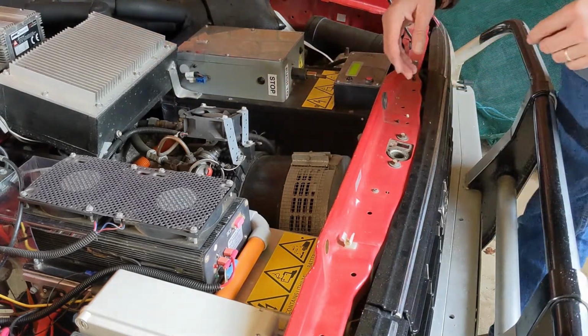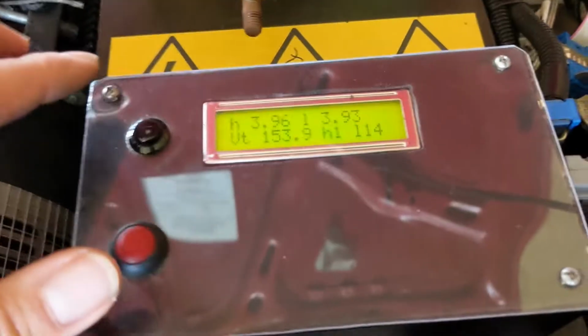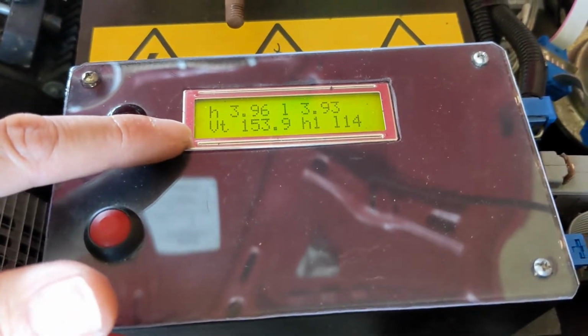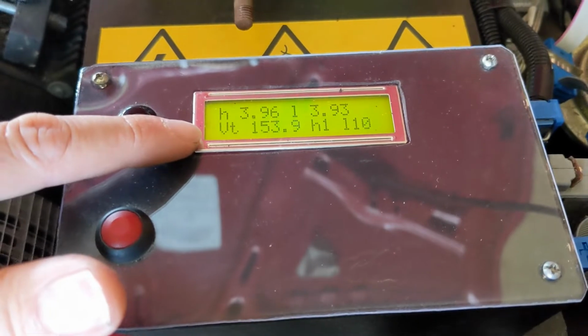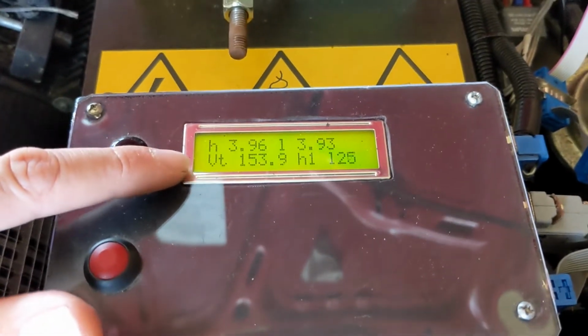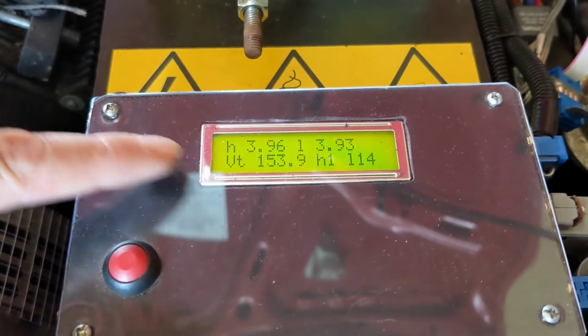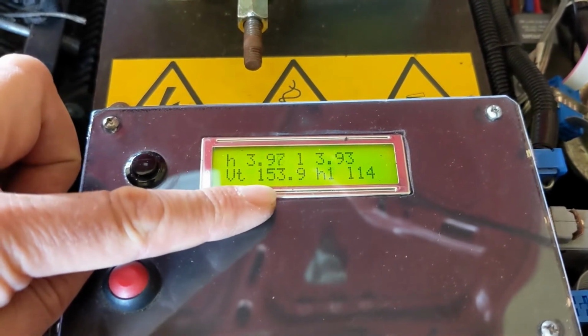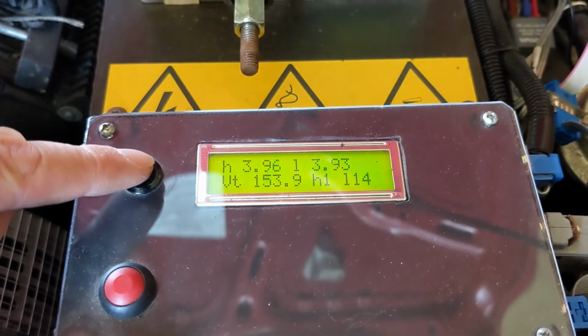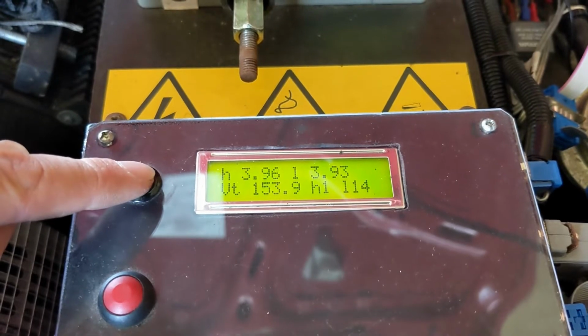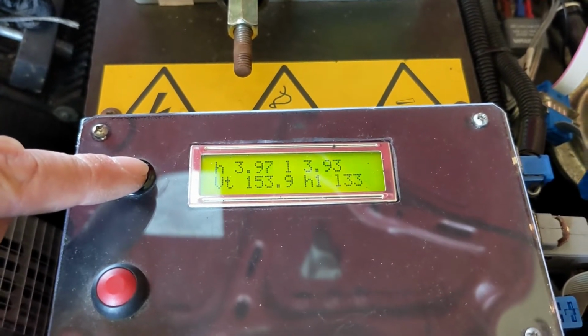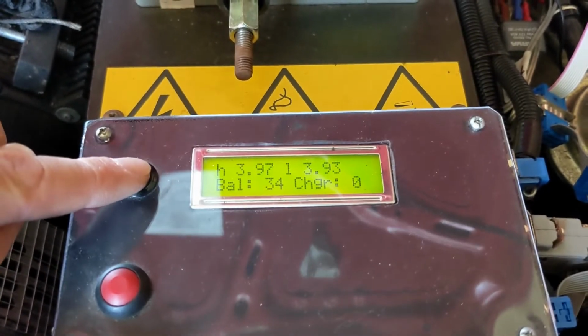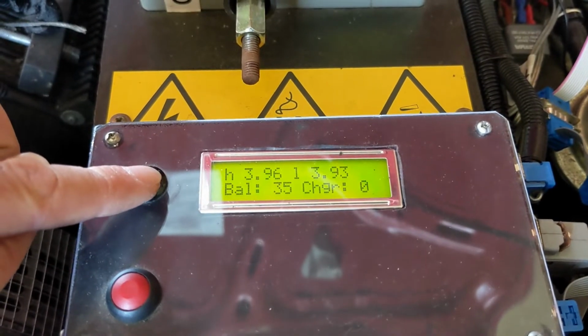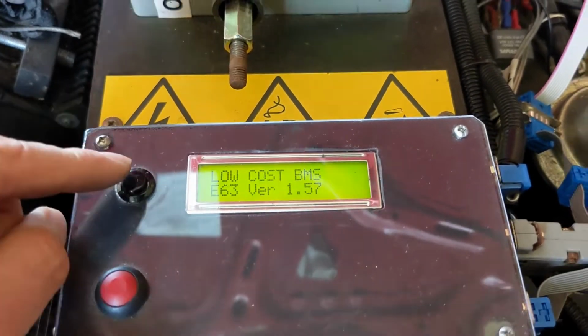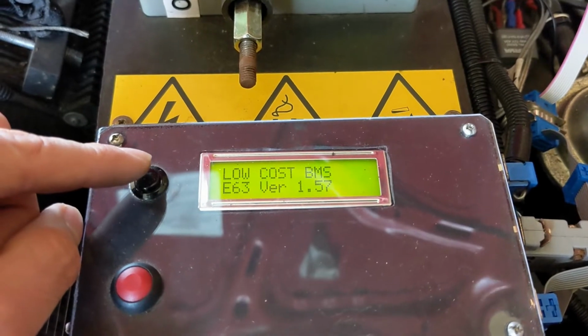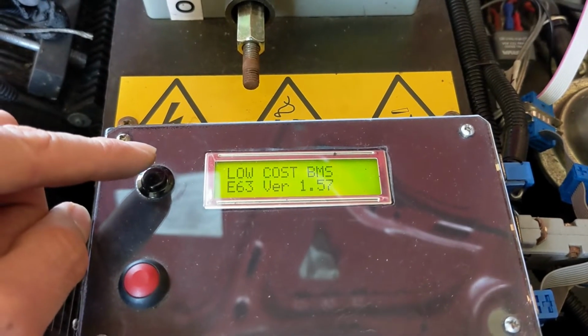I'll show you what the BMS is doing. So the BMS is perfectly happy with those 4 cells gone. So there's 4 cells now that are not in the loop. It's still reporting the high and low cell voltages. The total voltage is now 154 instead of, it was up around 170, something like that, 160 something. So it's just happily working away. It doesn't have as many cells, but it doesn't really care. So I'll go for a drive and see if I get any communications faults.